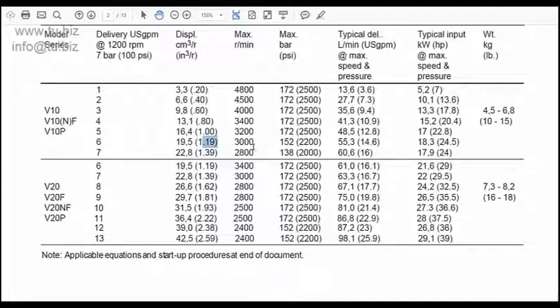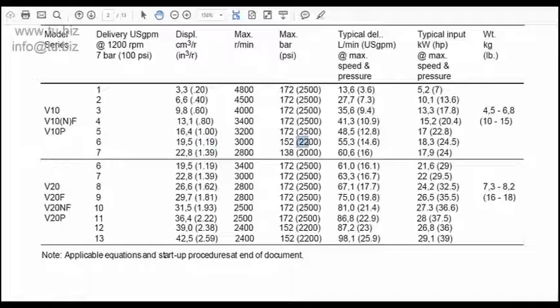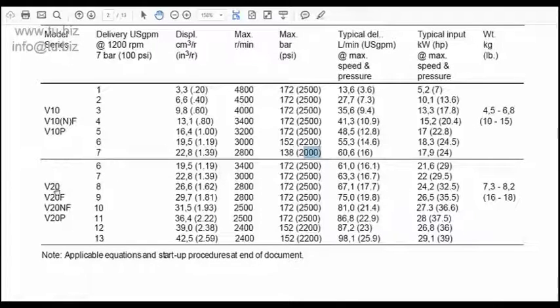Looking at the RPM ratings — these go 3000 and 2800, and I'm only working at 1800 RPM, so those are fine. For pressure, this one is rated at 2200 and the other at 2000 PSI. That's a bit tight on the bigger one since I'm working at 2000 PSI — I want some breathing space.